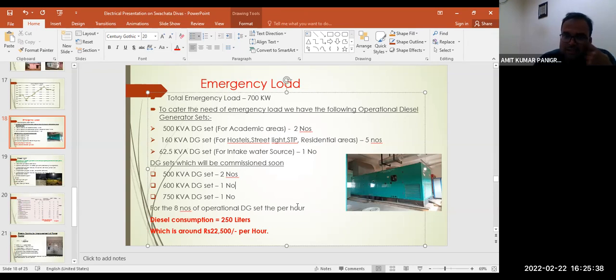So what is the cost of running these DG sets? If we run 8 DG sets of different capacity, our total diesel consumption per hour comes to 250 liters. If you take 92 rupees per liter of diesel, it comes to around 22,500 rupees per hour. So in case of power failure in the NISER campus, we are spending 22,000 rupees per hour to cater to the emergency load. In the future it will increase up to 40,000 because another 4 DG sets are coming. So that is about emergency load.